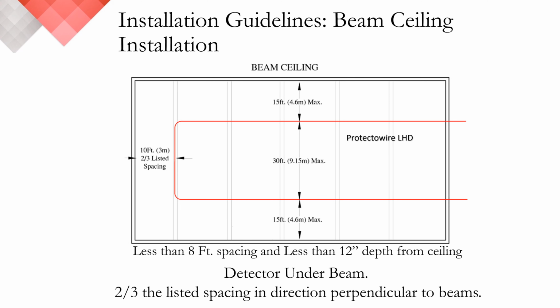In the case of beam construction, where the beams are 4 inches, 100 millimeters, or less in depth, the ceiling shall be treated the same as the smooth ceiling. If the beams project more than 4 inches, more than 100 millimeters, below the ceiling, spacing at right angles to the direction of beam travel shall not exceed 2/3 of the smooth ceiling spacing.